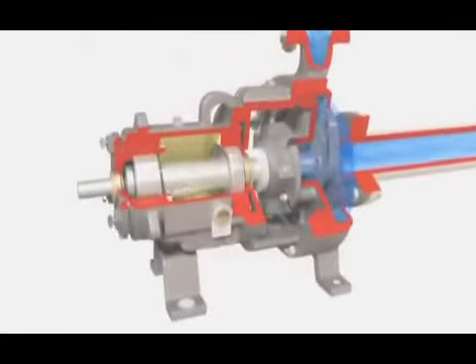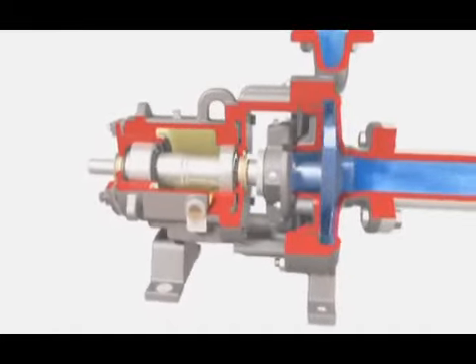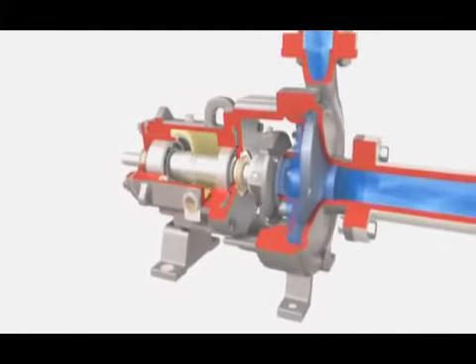Low, predictable seal chamber pressures and thrust loads resulting from the back vane pumping action and balance holes result in ideal operating conditions for mechanical seals and pump bearings.